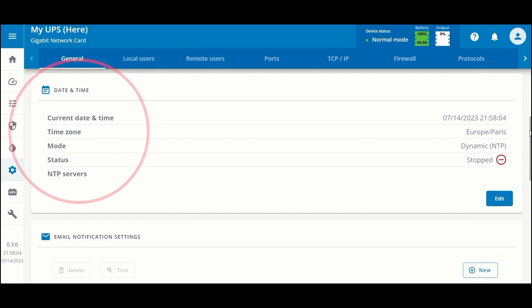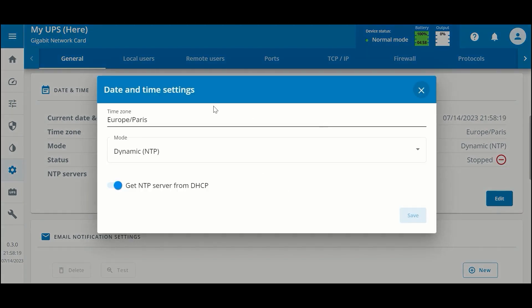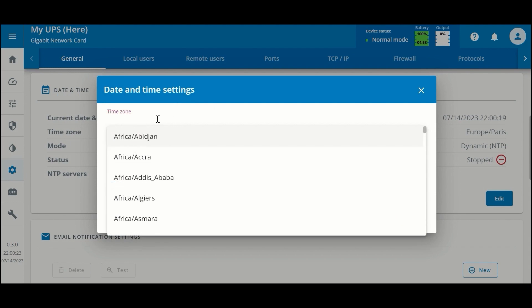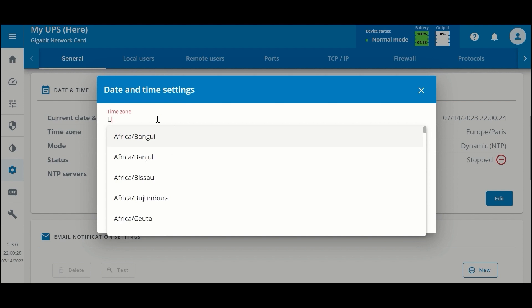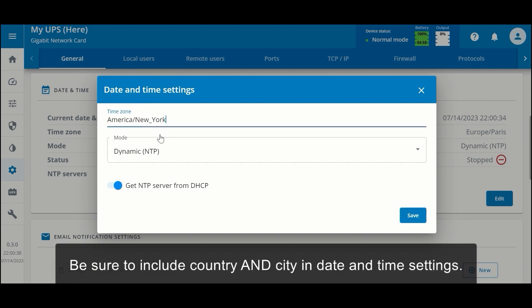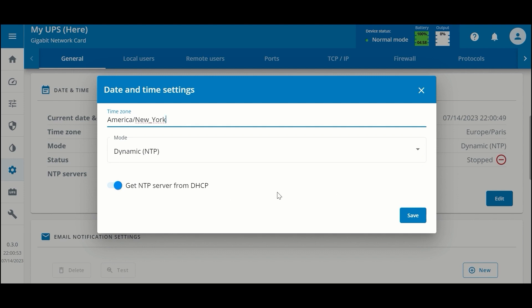For current date and time, we can edit this. Make sure that you type in the correct time zone for you. This is an auto-complete field, so you would start with your country and then the city. This is a good option for the eastern time zone in the United States. By default, we're using a dynamic NTP and getting our NTP server settings from the DHCP server.